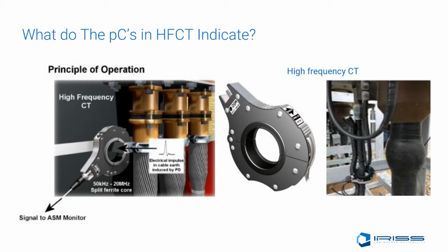The HFCT method is done while the component being tested stays energized and loaded. Another method of measuring these currents is to put a small current measuring resistor in series with the sample and then view the generated voltage on an oscilloscope via matched coaxial cable.